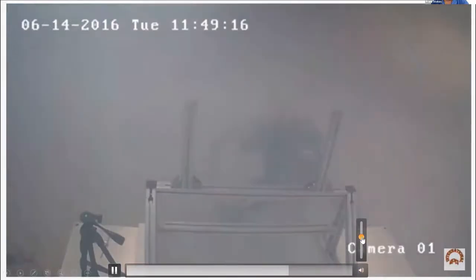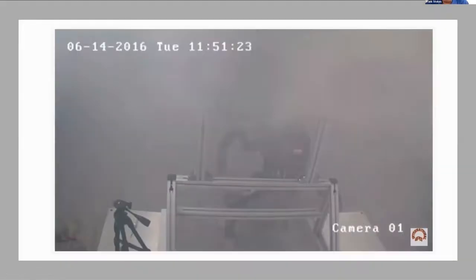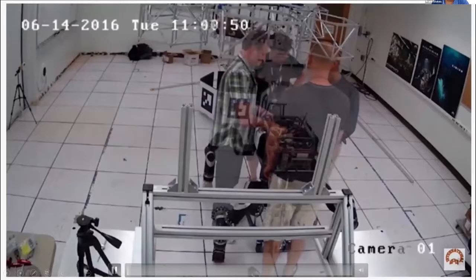The safety data sheet had called for a type D fire extinguisher and not to use water. There was no type D fire extinguisher available. One of the things we're learning is that a type D and a CO2 fire extinguisher are not effective in putting out these types of fires. One misnomer: in lithium-ion batteries there is not a lot of free lithium, so water is the best. Okay, so they showed that with a CO2 extinguisher, it's not very effective. But look at all the smoke, all the toxic fumes that person was subjected to trying to extinguish that fire. That exposure is pretty significant for those folks.